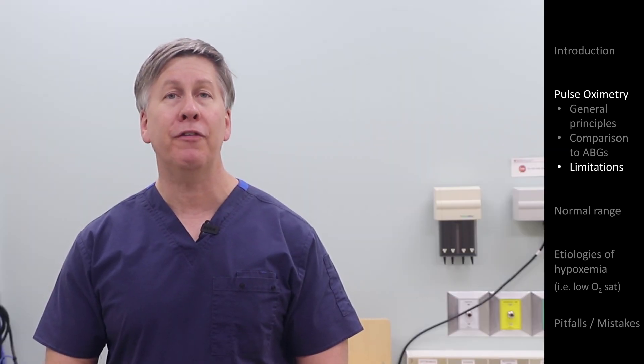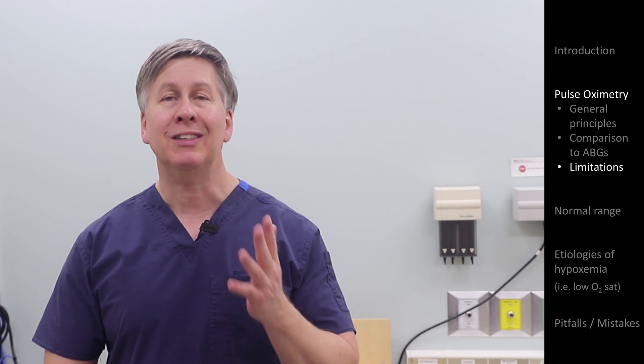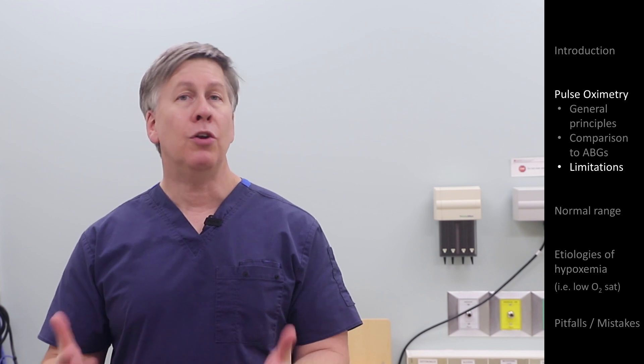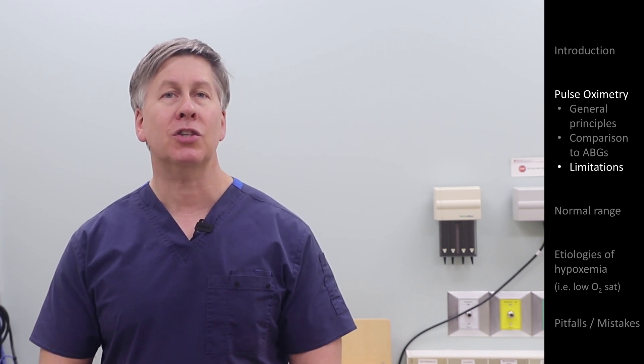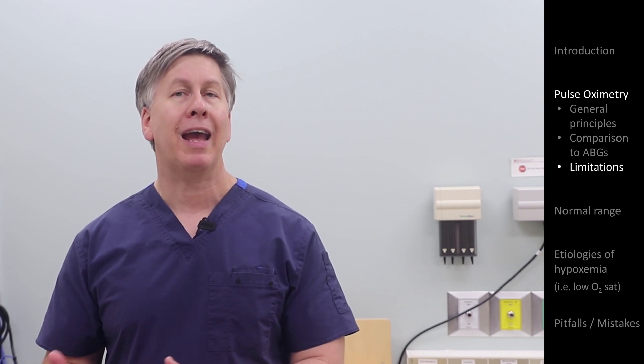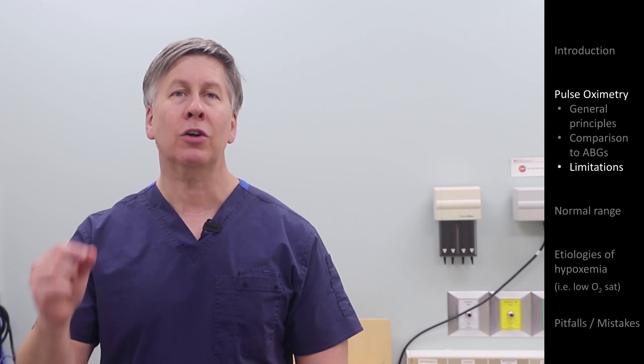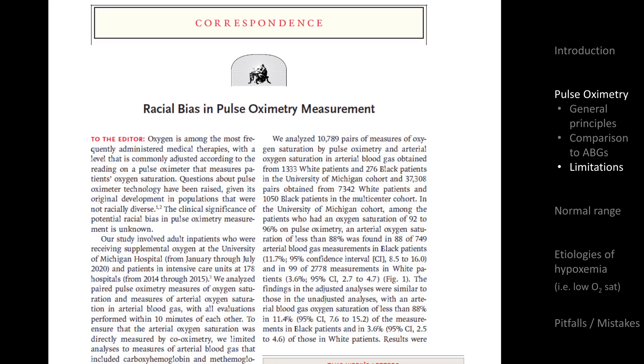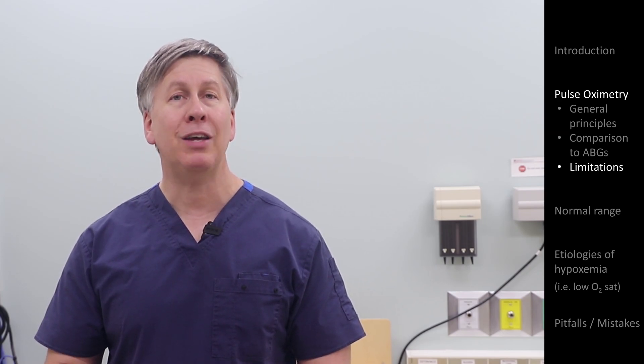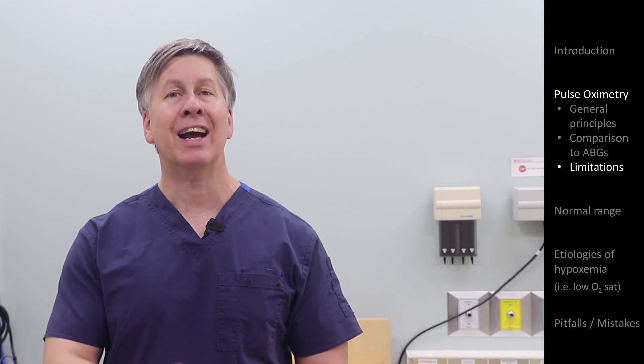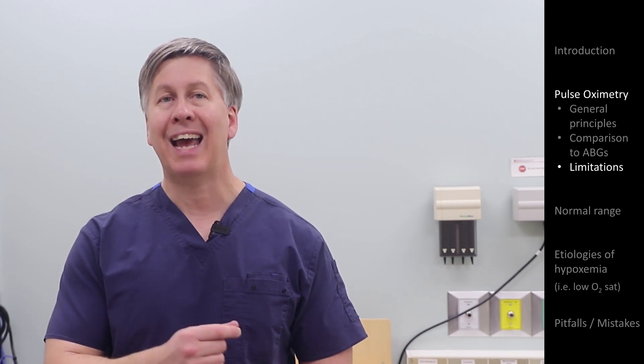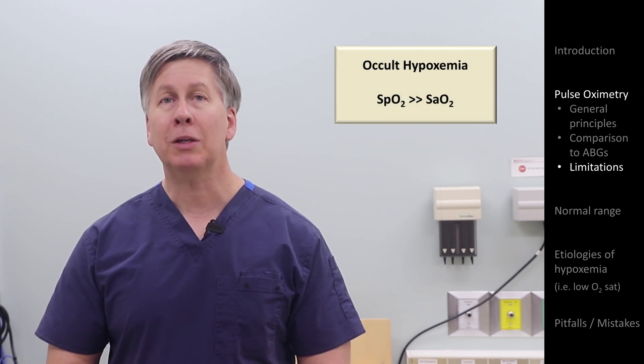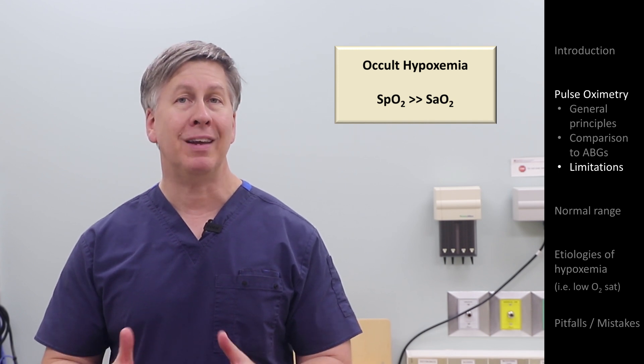One of the aforementioned issues deserves additional attention — the impact of skin pigmentation on accuracy. Although it had been known beforehand, widespread appreciation did not happen until 2021, when both traditional and social media picked up on a research letter published in the New England Journal of Medicine. What that letter described is that, compared to white patients, black patients were more likely to have SpO2 measurements significantly higher than the simultaneously measured SaO2. This phenomenon, known as occult hypoxemia, can result in black patients not receiving supplemental oxygen despite it being indicated.